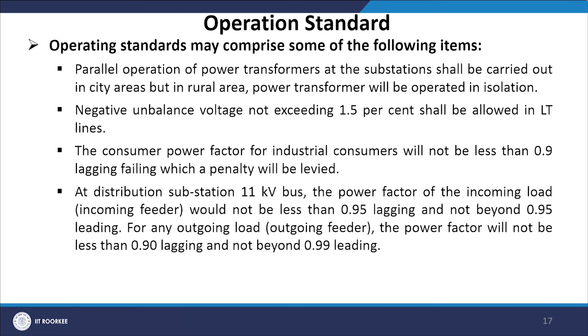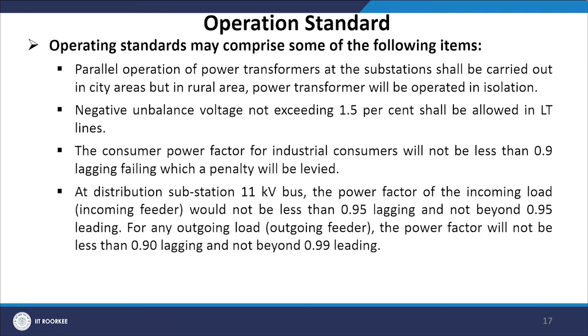Operating standards specify that parallel operation of power transformers at substations shall be carried out in city areas, while in rural areas transformers operate in isolation. Negative unbalanced voltage not exceeding 1.5 percent shall be allowed in LT lines. Industrial consumer power factor shall not be less than 0.9 lagging, with a penalty for violation. At distribution substation 11 kV buses, incoming load power factor shall not be less than 0.95 lagging and not beyond 0.95 leading; outgoing load power factor shall not be less than 0.9 lagging and not beyond 0.99 leading, ensuring reactive power requirements are met.